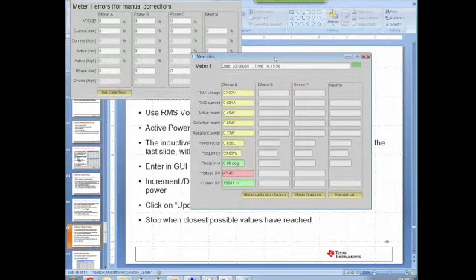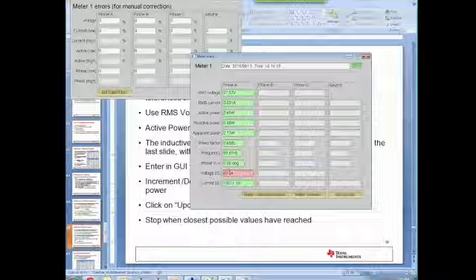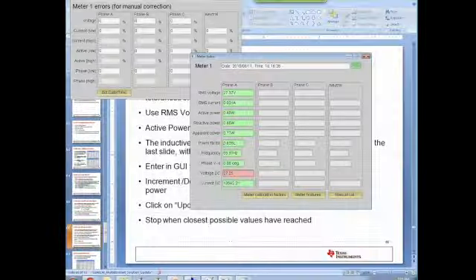So if you look at your meter status, you're going to start seeing active and reactive numbers that are a bit different than what you had before. Previously, the reactive power on those wire-wound resistors was about 0.1, while your active power was in the watt range. Now they should be approximately equal, but again, they're not quite right. So we're going to have to calibrate this. The other one that we look for is the power factor. My power factor is reading 0.63, which is a fair bit off from the 0.7 that we need.